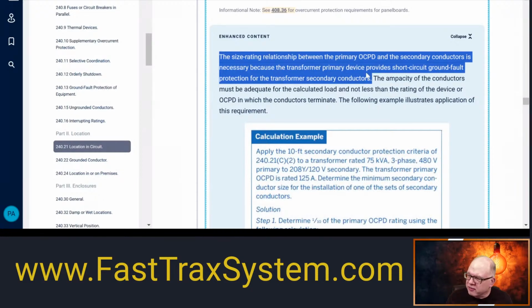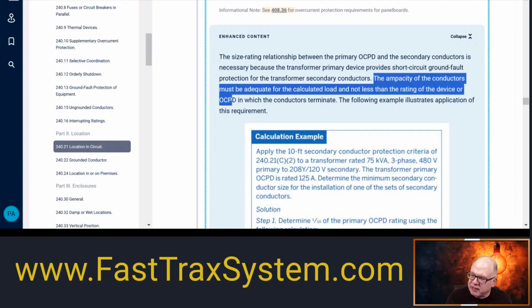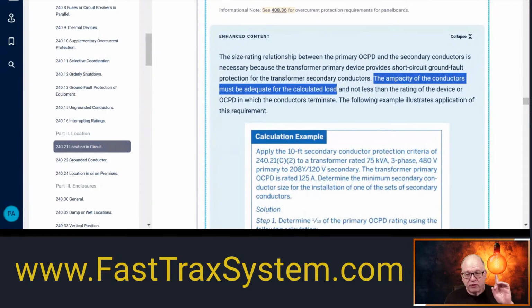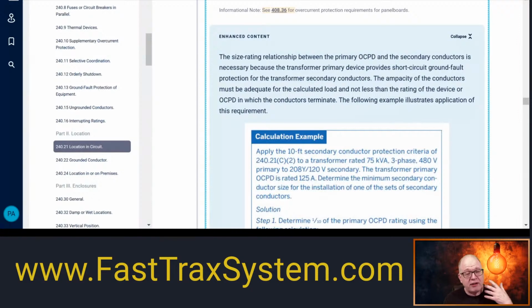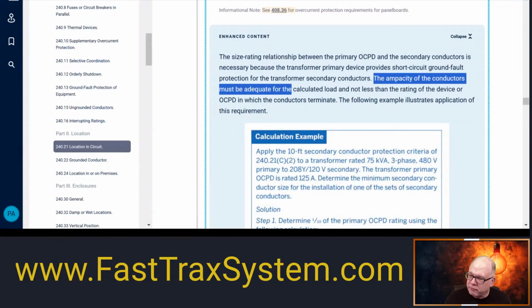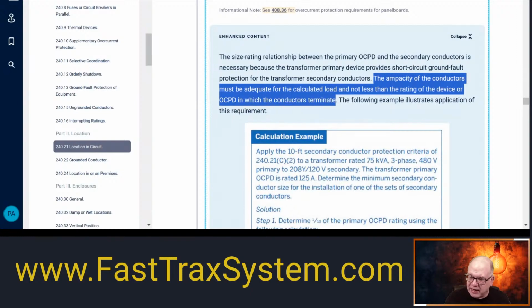Okay, so it says the ampacity of the secondary conductors must be adequate for the calculated load. Those conductors have to be sized for the calculated load, assuming you did a load calc. Hopefully you did that when you sized your transformer to make sure you got the right size transformer, right? At least you have to do that first. Make sure you know what the loads are, right? And it says the ampacity of the conductors must be adequate for the calculated load and not less than the rating of the device or overcurrent device to which the conductors terminate. Okay?